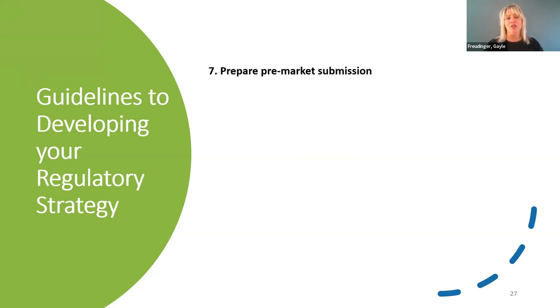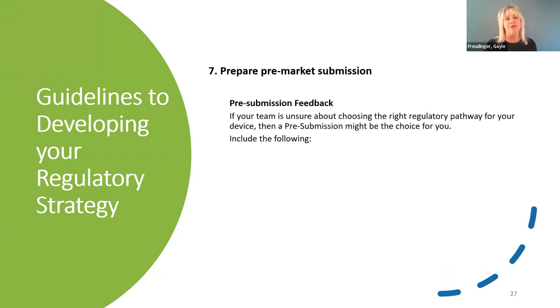Preparing a pre-market submission. Interacting with the FDA is always important, and you have the opportunity to do what they call a pre-submission process. That's establishing dialogue between you and the FDA. A pre-submission process is usually a good idea no matter what, but particularly if you're really unsure about the regulatory pathway, not sure if it's a 510(k) or PMA, and maybe you have a bunch of questions about the types of testing that you need to do. Maybe you found a predicate, but you still don't understand how to explain the difference or why your product is better, et cetera.